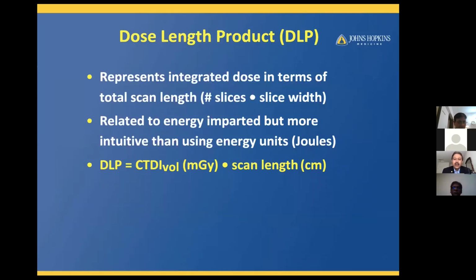Having said that, when you're talking about the patient dose, we are not confined to doing only one single slice. We do a number of slices, and that's incorporated into this concept called dose length product, also called DLP. The DLP is basically a product of the CTDI volume multiplied by the scan length. And this particular DLP is important because it shows us the total energy imparted to the body, and that can be used for estimating the risk. That's why the DLP becomes very important.